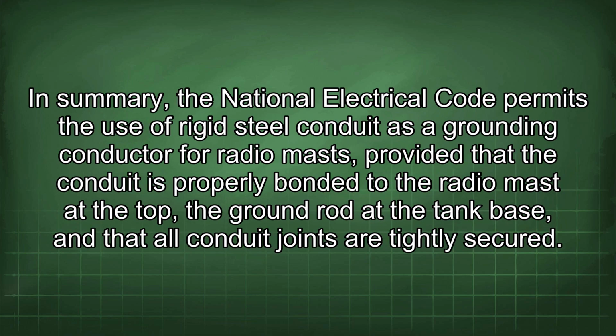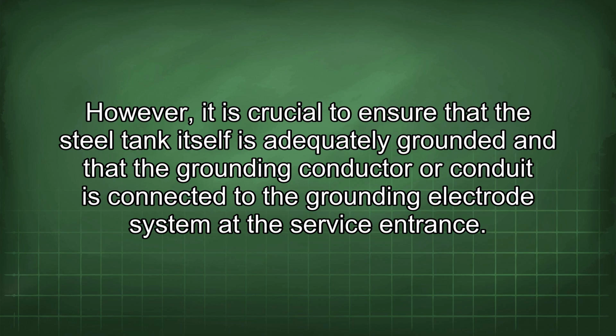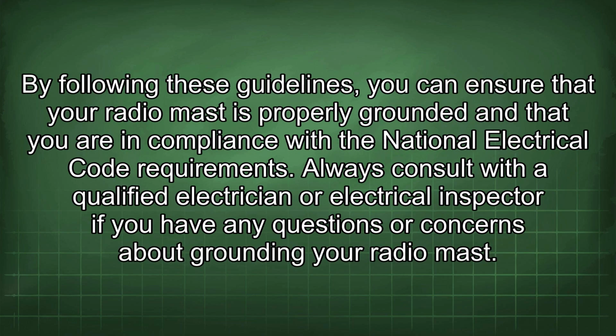In summary, the National Electrical Code permits the use of rigid steel conduit as a grounding conductor for radio masts, provided that the conduit is properly bonded to the radio mast at the top, the ground rod at the tank base, and that all conduit joints are tightly secured. However, it is crucial to ensure that the steel tank itself is adequately grounded and that the grounding conductor or conduit is connected to the grounding electrode system at the service entrance. By following these guidelines, you can ensure that your radio mast is properly grounded and that you are in compliance with the National Electrical Code requirements.